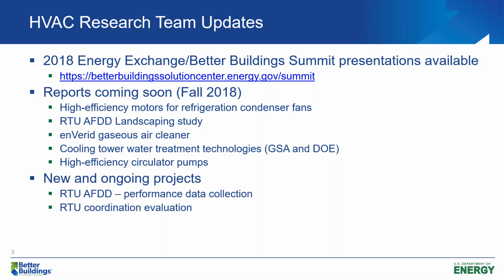And then some new and ongoing projects. We're going to continue with the RTU AFDD, and this year we're going to focus on collecting actual performance data from rooftop units. So that'll be exciting. And if you have projects and you'd like to share information, please let me know. And then we're also going to be starting up RTU coordination. So what that means is coordinating the control of rooftop units on a single roof. So instead of individual control, you'll control them kind of as a system so that you can manage energy and demand performance of those rooftop units.